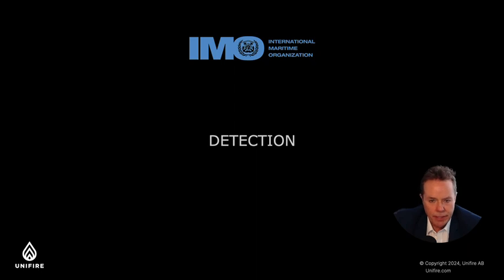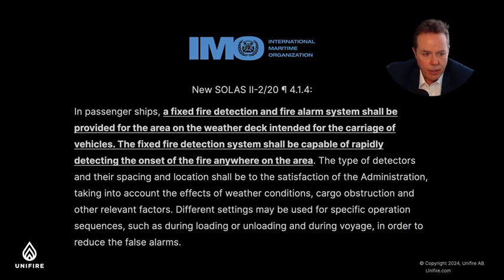So regarding the detection, the wording is that a fixed fire detection and fire alarm system shall be provided for the area on the weather deck intended for the carriage of vehicles. The fixed fire detection system shall be capable of rapidly detecting the onset of a fire anywhere on the area. So this is quite generally worded, and I think that's good in a way. It allows different detectors to be used.